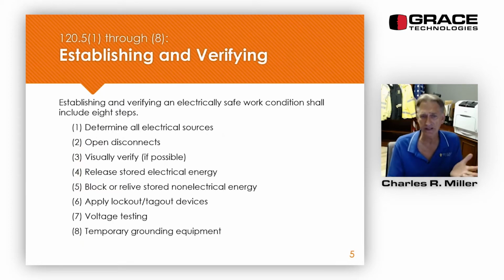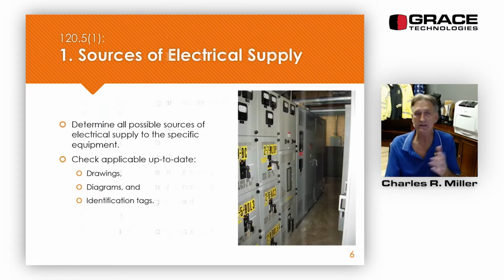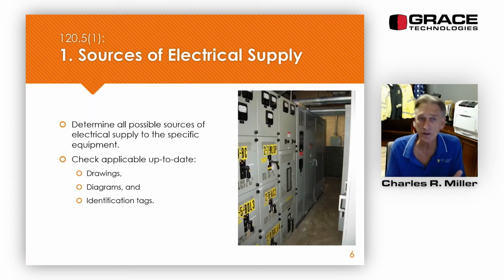All right, here are the 8 steps. Determine all electrical sources, and I'm just going to go over these quickly because we're going to spend a little more time on each one. We're going to open the disconnects. We're going to visually verify, if it is possible. It's not always possible. We're going to release stored electrical energy. We're going to block or relieve stored non-electrical energy. It used to say mechanical energy, but the committee changed this in the last edition from mechanical to non-electrical. We're going to apply lockout tagout devices. We're going to test for the absence of voltage, and if necessary, we're going to put on temporary electrical safety grounds. Now, this is set in 70E, section 120.5, and our 7 or 8 steps are in this section 120.5.